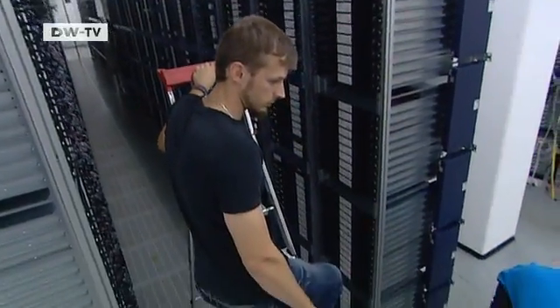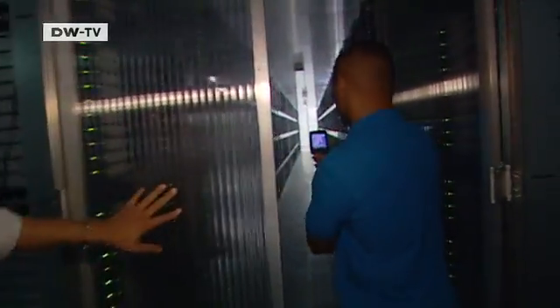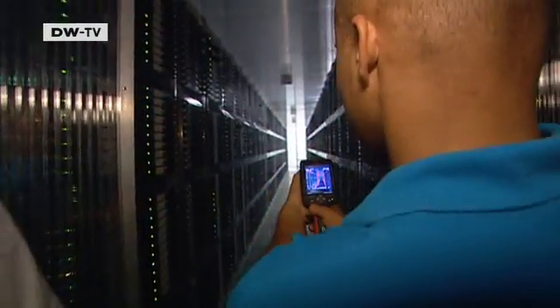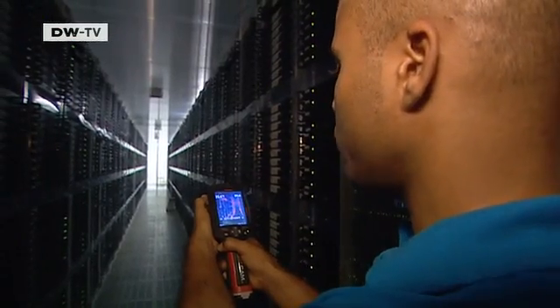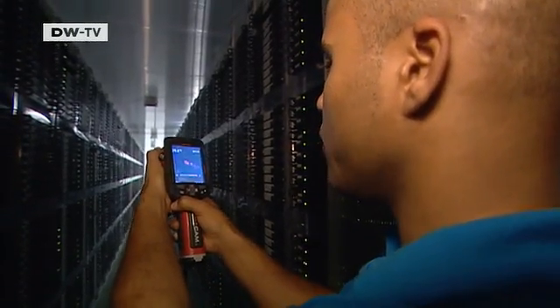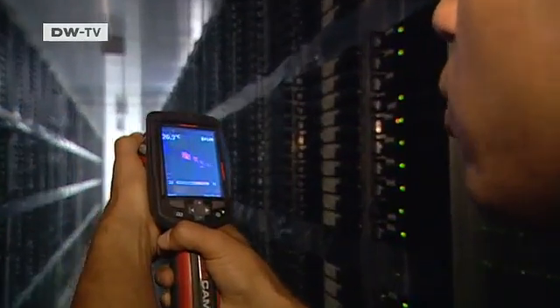The cloud is even larger now. Daniel Brooks carries out a final check using a thermal imaging camera to confirm the cold aisle is airtight. As you can see, it's 25 degrees Celsius at the warmest point on the computer. Now it's being adjusted — you can see where it really is warm and where something needs to be sealed off. Up there it's 30 degrees, and there you can see the leaks that still need to be sealed.